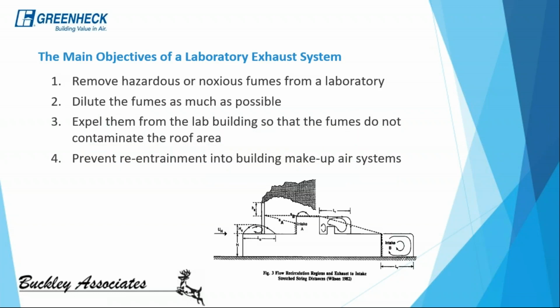So what differs a general exhaust fan from a laboratory exhaust system? Why would we need to use a lab exhaust fan instead of a standard upblast or downblast fan? The problem here is that in these systems, we're typically exhausting air that is highly contaminated by either hazardous gases that need to be diluted or air coming from hazardous areas such as pharmacies, or today, like we're talking, isolation rooms. So when we're selecting these systems, we really have four main objectives we need to pay attention to.